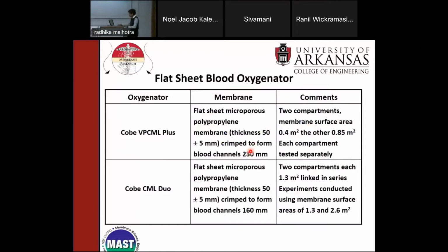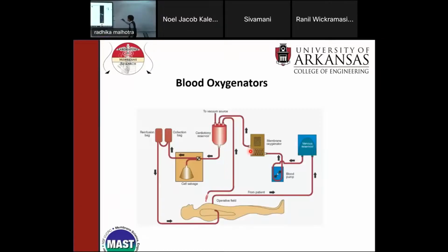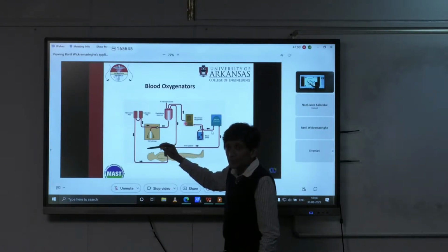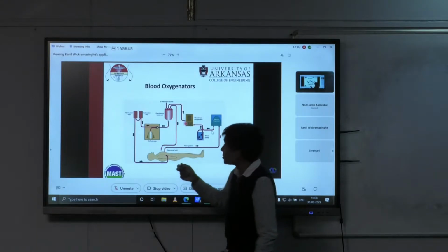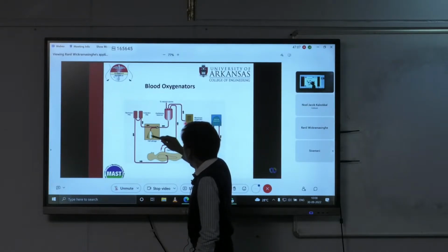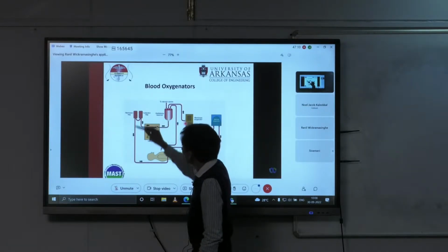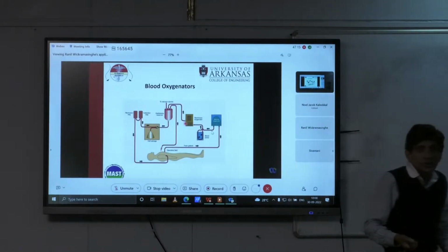And let me see if I can go back to my very first or second slide. Yeah. So when you're going through this procedure, you can imagine you're taking blood out of the patient, okay? It's going through this venous reservoir, through a blood pump, through the oxygenator. There are various filters all over the place, by the way, filters to remove emboli or blood that's clotting, okay? It comes into the cardiotomy reservoir. From there, it comes into the cell salvage if we're having it, collection bag, reinfusion bag, and typically a lot of anticoagulants are added because you don't want the blood to start clotting.